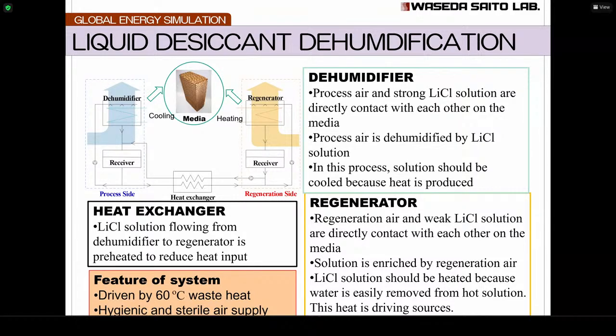So that's why we have to regenerate that. We move the liquid desiccant to the regenerator with some pumps. And in the regenerator, regeneration air and weak solution directly contact each other on this media packed bed. And the solution is enriched by regeneration air. The LiCl solution should be heated because water is easily removed from a hot solution. So that's why we have to heat up in this regeneration process. And this is the driving source of this total system. But the important point is we need only 60 degrees Celsius heat to drive these systems. This means we can sometimes use waste heat or solar thermal energy. So if we drive this system with this kind of waste heat or renewable energies, the performance of this system is very high.